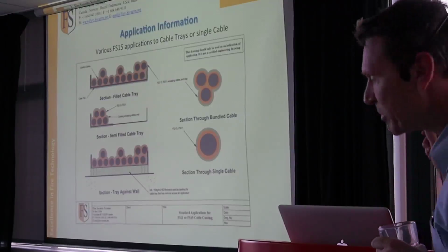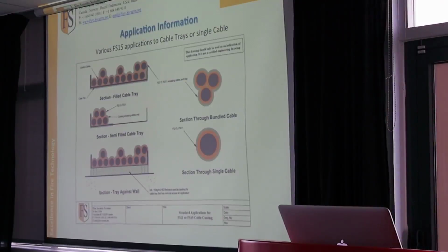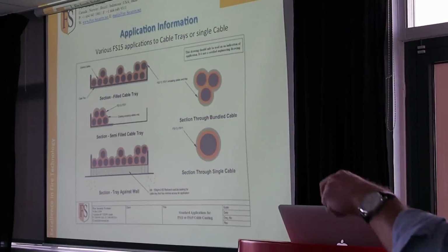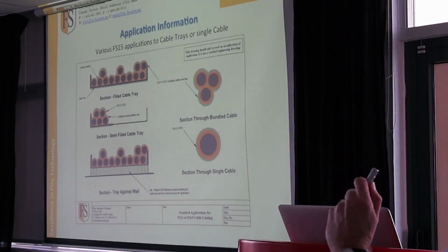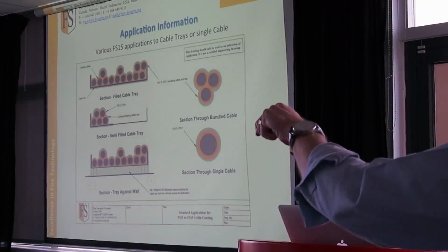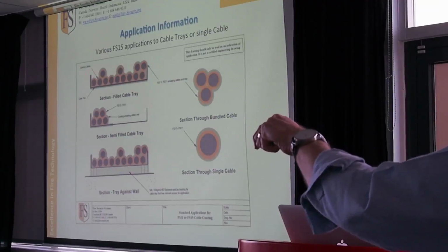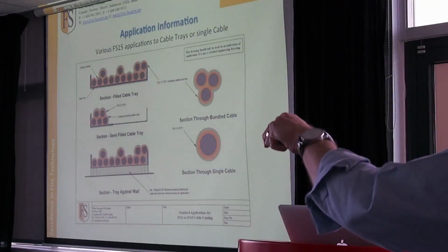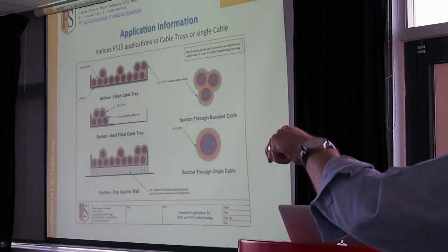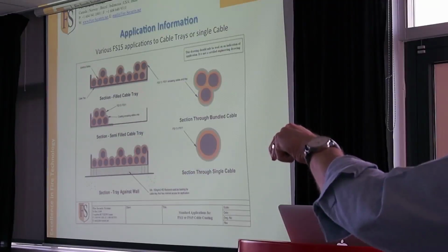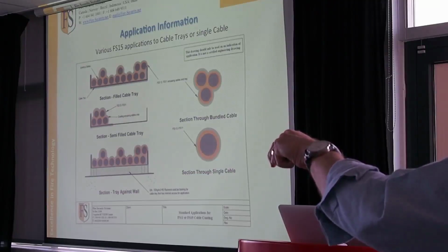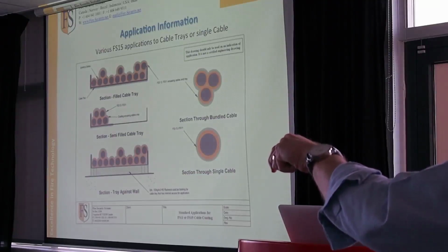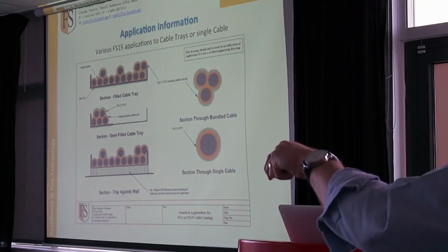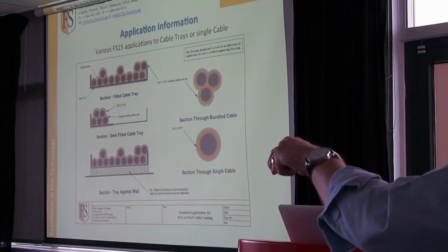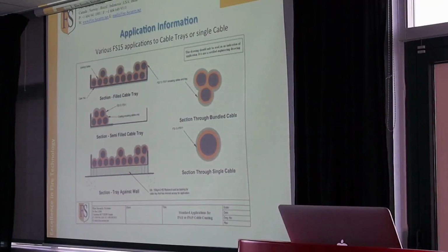So for types of applications of coatings, a fairly typical application is a fully loaded tray where we simply just coat the exterior surface of the tray, so flame will not burn along the surface. If we're finding cable trays like this with a certain amount of cable in it but not fully loaded, then we'll only do the sectional area of it. There's no need to spray over here. And you have to remember, we're only here to protect the cables.